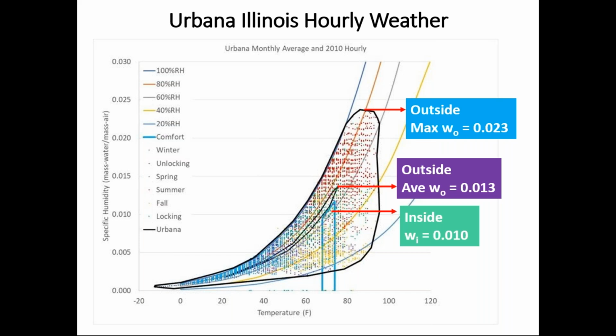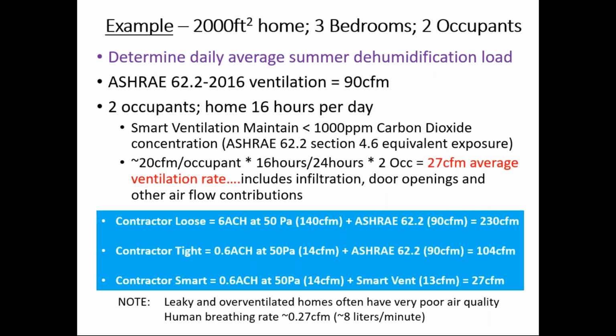But when we also look at how much humidity we might reach in our location, and actually Miami, Florida, New Orleans, Houston, their peaks are not much different than our peak, as I mentioned. It's just that they have more hours located in that upper range, that they might reach a humidity ratio of about 0.023. So when you look at the difference between 0.013 and 0.01 versus 0.023 to 0.01, you can see that the humidity handling, the moisture handling capacity of a machine can vary greatly from one day to the next.